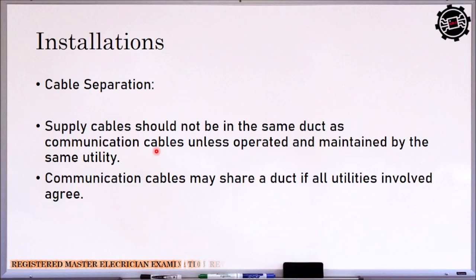So exception for that one, if the operating voltage is not more than 300 volts between conductors, so that is phase to phase. And also there must be an agreement between the utility companies, between the owner of the cable and the steam or gas pipelines that will pass there.